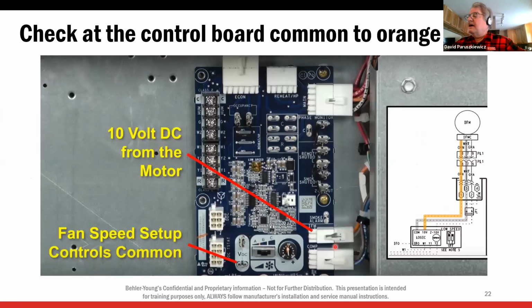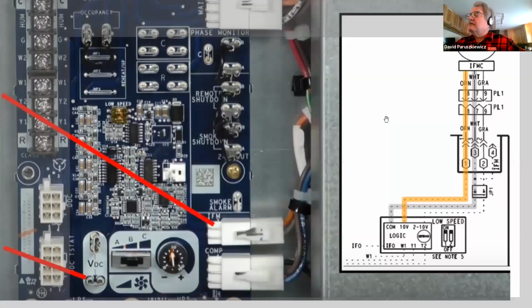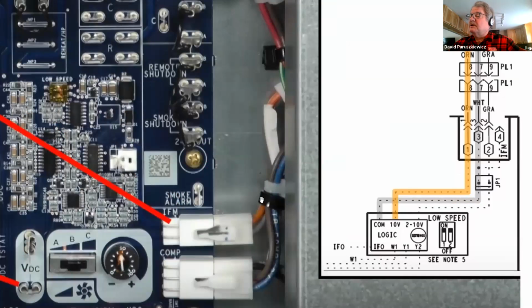All right, now low voltage. So the motor gets line voltage all the time. Then it creates a DC voltage. The motor actually creates a DC voltage, which comes back up this orange wire. See the orange wire right here? To the board. So the 10-volt DC comes back from the motor up this orange wire right here. So this little metal tab right here, that's 24 volts or 10 volts DC.